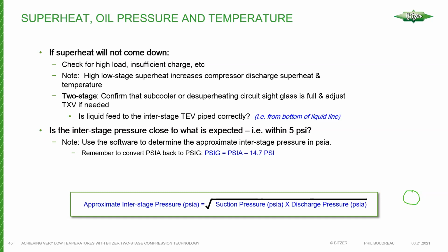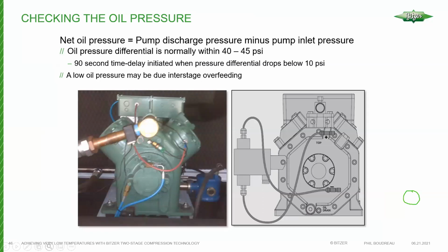If your interstage pressure is riding lower or closer to the suction pressure, that's an indication that you should probably open up that compressor, specifically on the low stage side. Take a look at the gaskets, take a look at the valve plates. You just may have a problem there. On the other hand, if the interstage pressure is operating closer to the high stage pressure, that means your compression ratio on the high stage isn't as high as perhaps what it should be. So perhaps, again, we have a problem with gaskets where it's blown from the high side to the low side of the cylinders, or the valve plates have been damaged, because too much interstage flow can cause that.